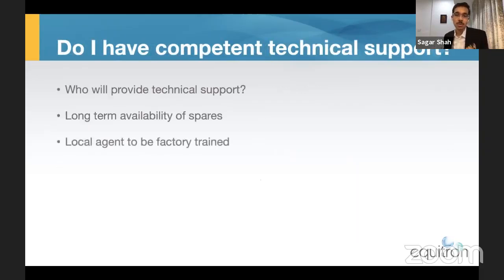Going to the next question, have you checked whether you're receiving technical support for the autoclave? Now, one thing is for sure, the majority of people do not anticipate downtime. But when your autoclave isn't functioning properly, you want to be sure that the technical support that you get is competent and it is provided promptly. Downtime is costly, both financially and for your lab's productivity. It's best to inquire with your manufacturer about who would provide technical support in your region and when it's going to be available. When is the technical support going to be provided? Is it going to be provided within 48 hours of the complaint, 24 hours, 72 hours?